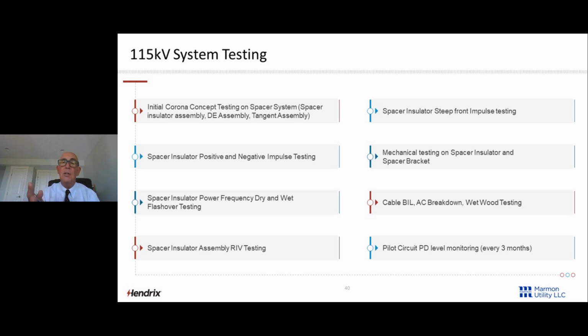We did spacer, insulator, steep front impulse testing. We did tons of mechanical testing on the spacer, insulator, and the bracket. We did cable BIL, AC breakdown, and wet wood testing. And we did field testing on our pilot circuit every 3 months, probably for the last close to 4 years.